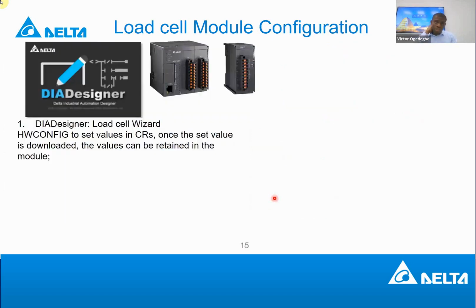Okay, that's for that. Then how do we program the load cell module? I think I see one of our colleagues on the call, Shami, you already have experience with the load cell module. Maybe some of us here, this is your first time with the load cell module. So what are the options you have to program and configure this device? One of the options is DIADesigner. In DIADesigner, there's an integrated load cell wizard, the LC wizard. If you start the LC wizard, you can set the parameters of the load cell module in compatibility with the specification of your load sensor. So you set it up in the load cell wizard.